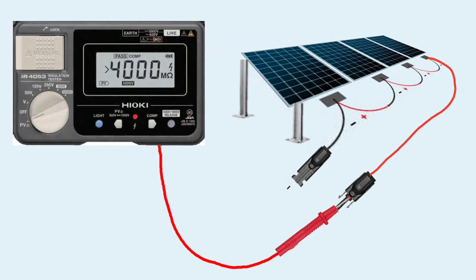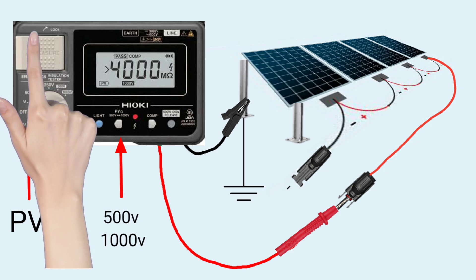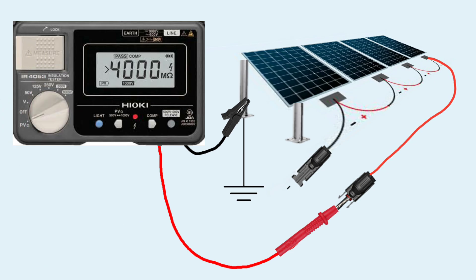Connect the positive MC4 of the PV string terminal to the red electrode of the device, and connect the black electrode to the system body earthing. Set the testing voltage at which you want to test the PV string, turn the knob to the PV resistance setting specially provided on this device, and hit the test button. The value is measured in 4 seconds and you will get the resistance value between the PV cables and the system earthing.